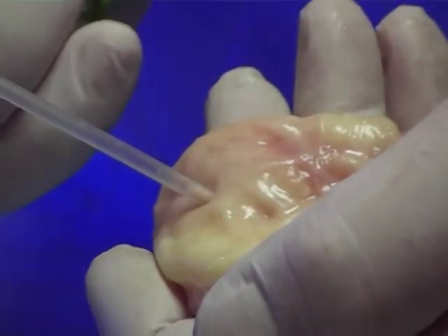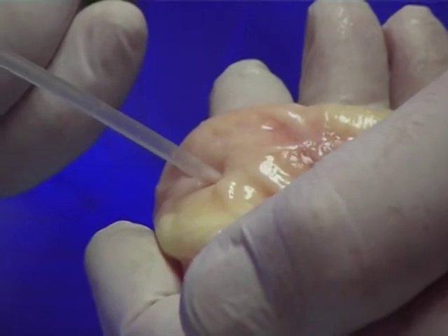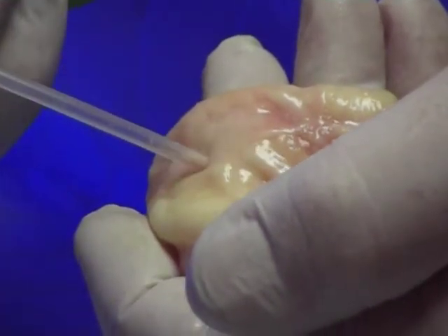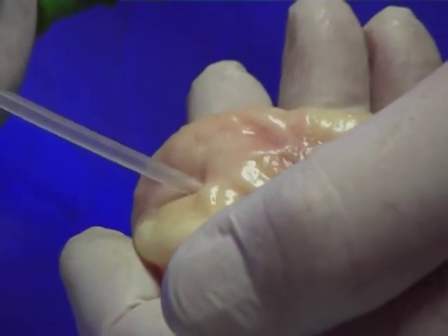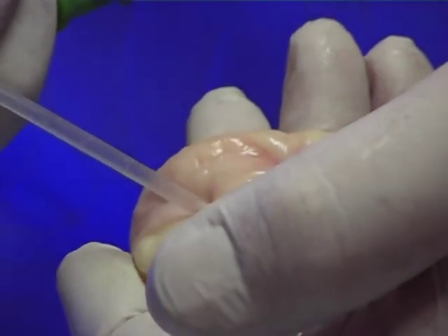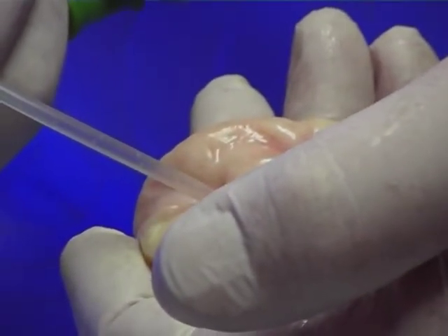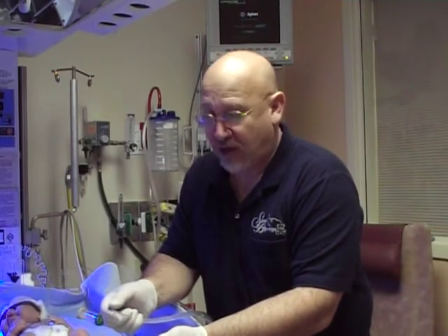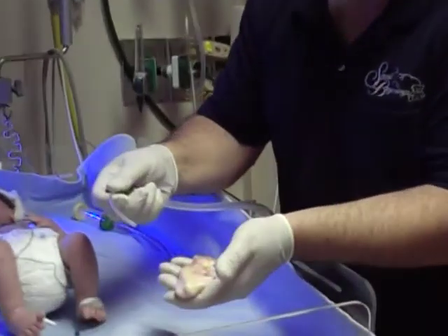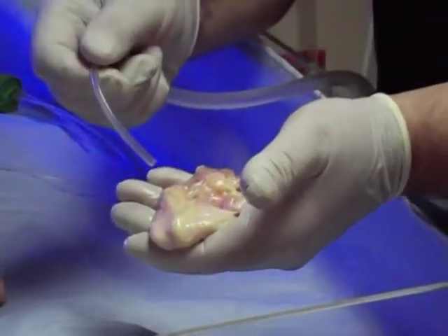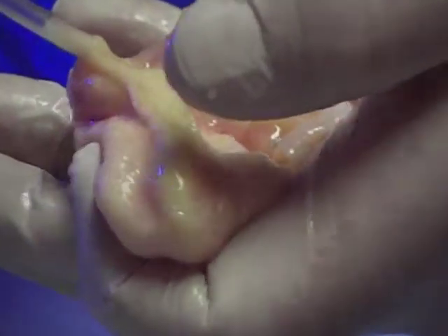Now nurses will tell you, well, I need something that will get the mucus out quickly, so even though this device is cut down at the bottom level, a lot of times they will take this and cut it again and use the larger portion, and I'm going to show you what happens when you do that. Next thing I'm going to show you is what happens when a nurse cuts the device even shorter in order to try and get the secretions quicker. Whenever you cut a device, you make a sharp edge to it, which can actually cut into the mucosa of a neonate. But just to watch and see what happens when we take a larger hole device and put it in there, we actually move the device.